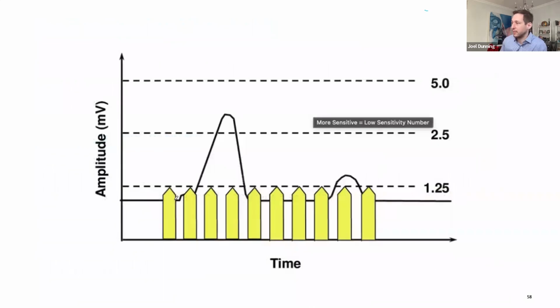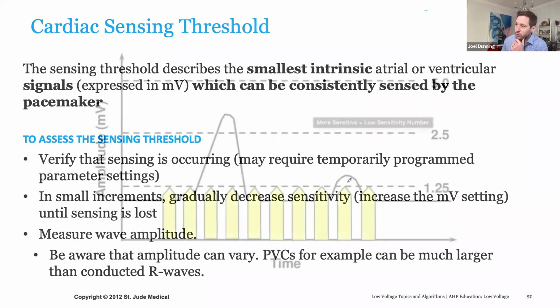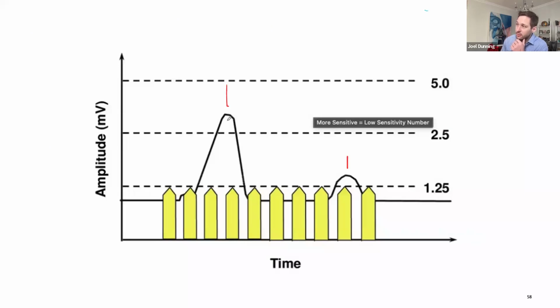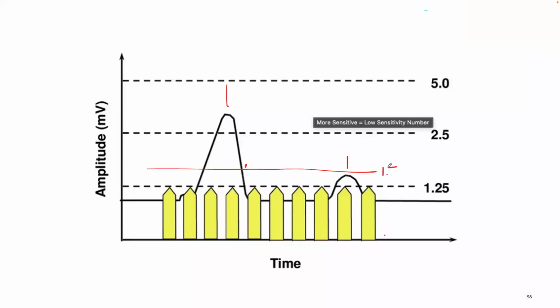So here's a good diagram. If you can see here, here's your R wave, here's your T wave. This device would effectively be double counting because the sensing threshold is set so low. So what we'll slowly do is raise this fence here until it's enough to consistently sense, but without over-sensing this T wave. And that will be your new sensing threshold. Then you'll actually set your setting at a 2 to 1. So in this case, this may be 1.5.